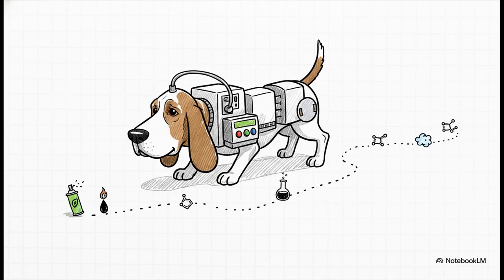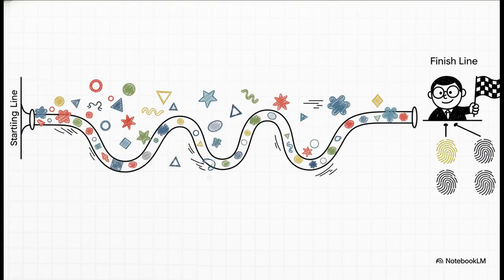Okay, next up, our sample moves on to the GCMS. If the ICP was our metal detector, this thing is the bloodhound. Its job is to sniff out a completely different class of troublemakers, organic pollutants like pesticides, fuels, and industrial solvents, what we call VOCs. The way it works is, honestly, like a chemical race. The sample gets injected into the super long heated tube, and all the different chemicals start racing through it at different speeds. And at the finish line, you've got this judge, the mass spectrometer, and it IDs every single chemical as it crosses, based on its unique chemical fingerprint.